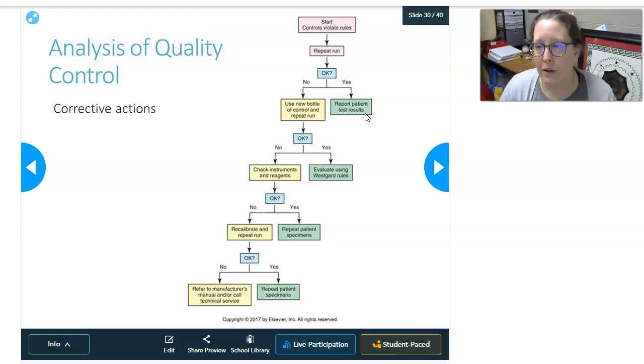If you reran those quality controls and they are not in, then your next step is to go get a fresh bottle of the level or the levels that you're having issues with. So that means you're going to go in the fridge or the freezer or whatever, grab some more, make sure they're at proper temperature and all of that, mix them really well, and load it again and run it again. Okay, if those worked, then you are going to want to evaluate it using your Westgard rules and go look at your Levey-Jennings and make sure what's going on with the test. Are we back in? Are we good to go? And then decide from that whether or not you can keep reporting patient results out.